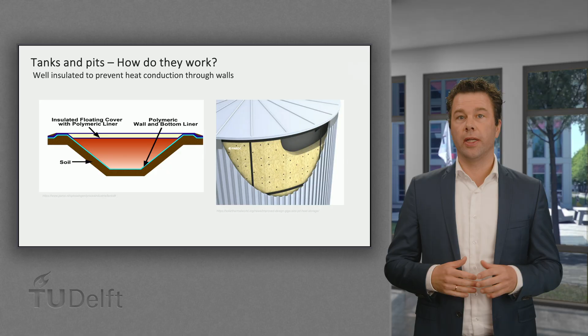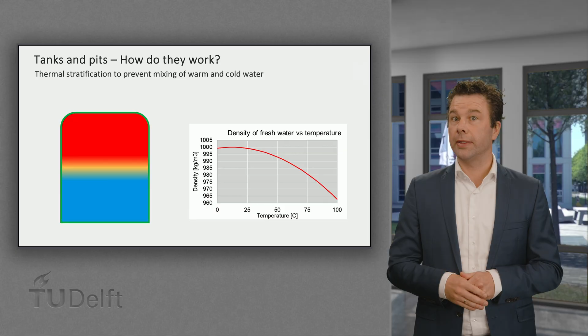Another important feature of tanks and pits is thermal stratification. During charging and discharging, the hydrodynamics inside the tanks or pits cause mixing and exergy loss. To prevent this from happening, inflow and outflow points at the top and the bottom are used to promote thermal stratification to occur. Due to the dependency of water density on temperature, the hot water with lower density remains at the top part of the tank and the colder, denser water at the bottom. The inflow and outflow points are often specially designed to inject and extract with little turbulence to prevent this mixing.